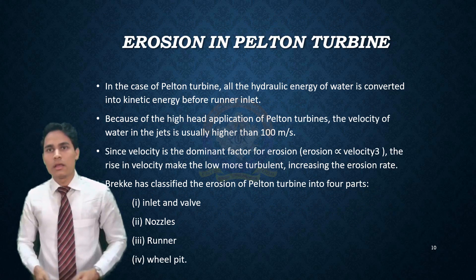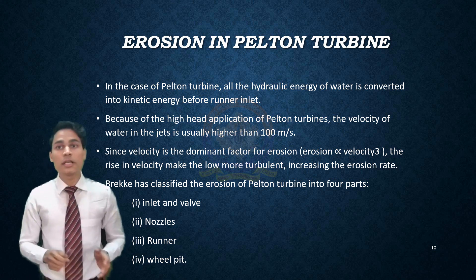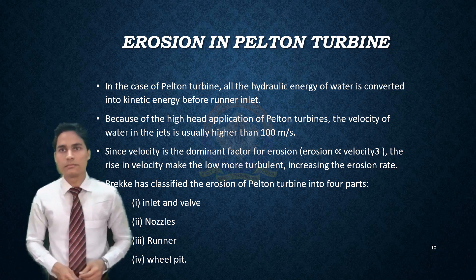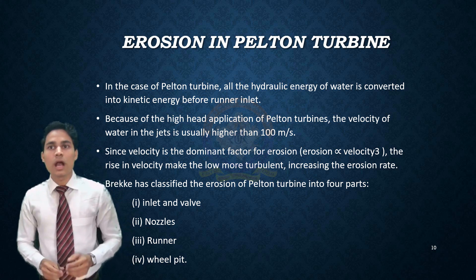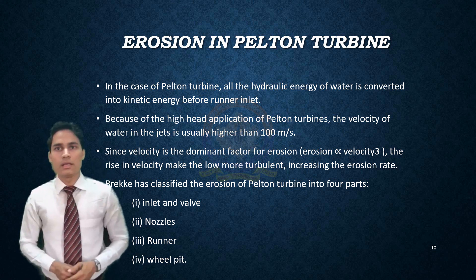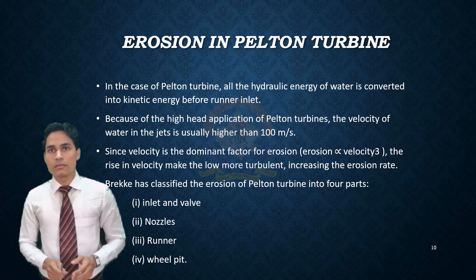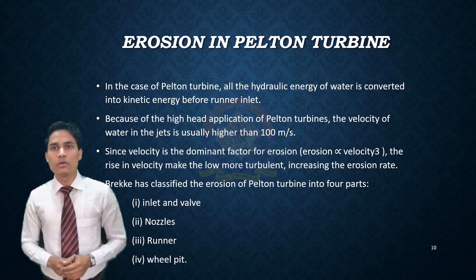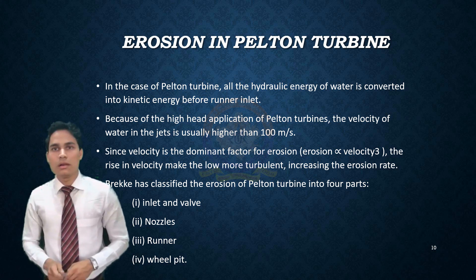Erosion in Pelton turbine. In the case of Pelton turbine, all the hydraulic energy of the water is converted into kinetic energy before the runner inlet. Because of the high head application of Pelton turbine, the velocity of the jet is usually higher than 100 m/s. Since velocity is the dominant factor for erosion, the rise in velocity means the flow is also more turbulent, increasing the erosion rate. Erosion of the Pelton turbine is classified into four parts: inlet and outlet valve, nozzle, runner, and wheel pit.